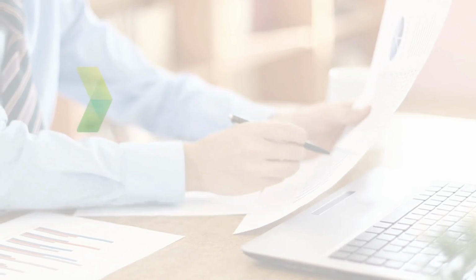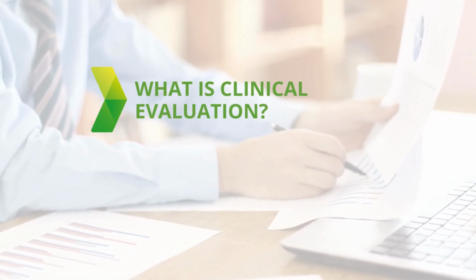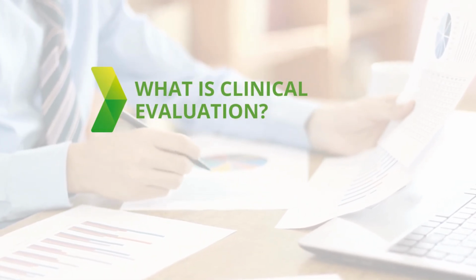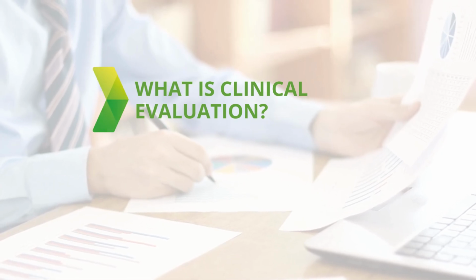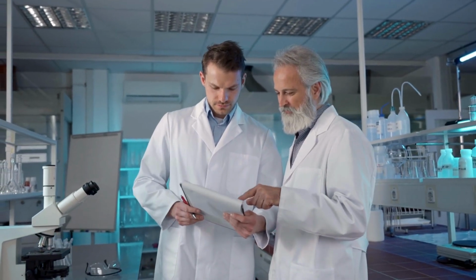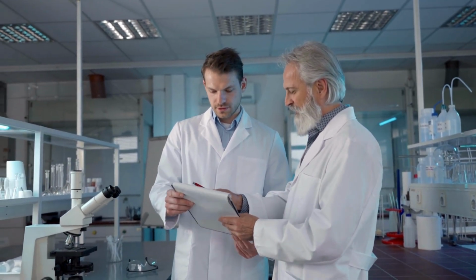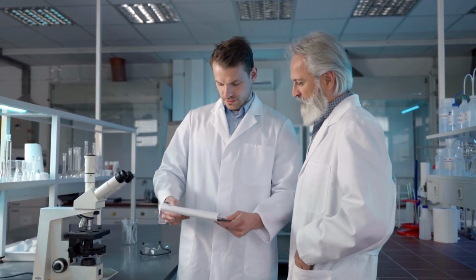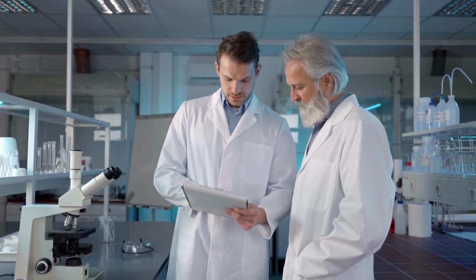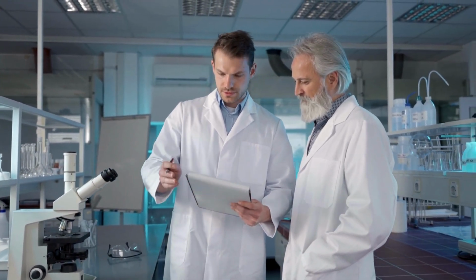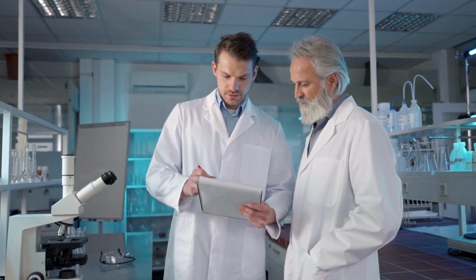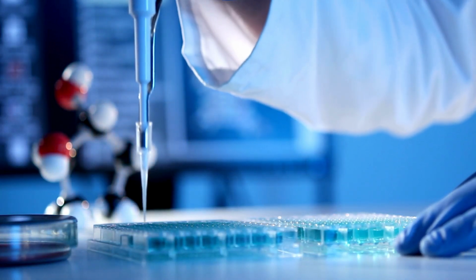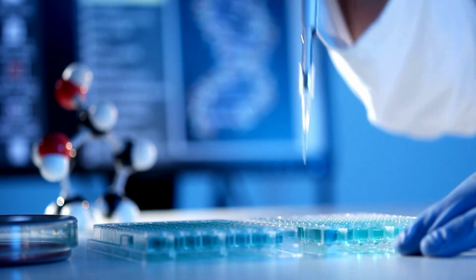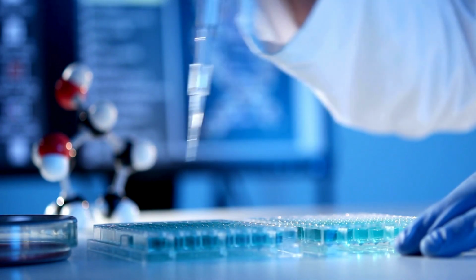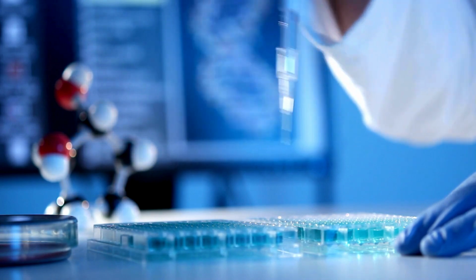Let's explore what clinical evaluation really means in the EU MDR context, the essential steps involved, and the main points manufacturers need to keep in mind to comply. Clinical evaluation is the systematic assessment of clinical data to verify a device's safety and performance. It's an ongoing process and must be maintained throughout the device's entire life cycle, not just before market entry. This aligns with the EU MDR's focus on ensuring that devices are effective and safe from launch through every phase of use. Under MDR, clinical evaluation is structured and highly regulated, covering both pre-market and post-market data.